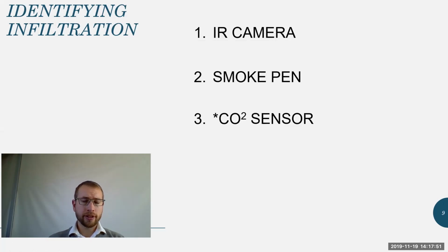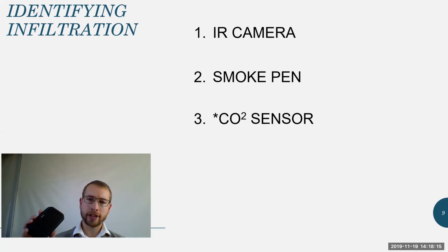So that means a lot of things can be missed within the building. And little gaps can show up within construction and have a really big impact on the energy use of that building over time. There are three tools that you can use to identify points of air coming into the building and causing excess energy usage. First is your trusty IR camera. Make sure it's calibrated and really focus it on a particular area within the building.